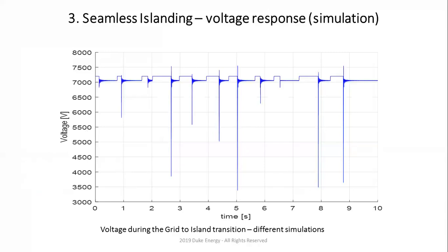So remember, I mentioned to you, this is simulation, right? This is what happens when you do seamless islanding. And as you can see, there are large voltage excursions. Our regular voltage is about 7,200 volts. That's 1 per unit, 120 volts on the secondary. But you can see that we have these voltage dips or voltage sags that go all the way down to even less than 50%. So the question is, why does that happen, right?